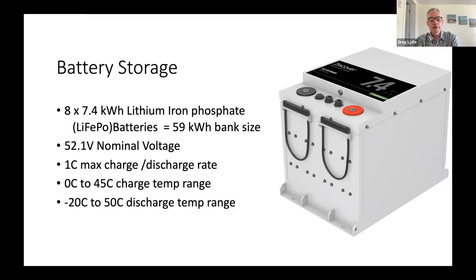The limiting factor here is the amount that the inverters can charge the batteries at, not the maximum charge current that the batteries can take. I think our inverters are rated at about 12.5 kilowatts for battery charging. So we could charge our system from essentially low batteries to 80% in about 4 hours of generator operation. I think the system's configured right now to charge the batteries up to about 80%. That can be tweaked up to 95% to get the full capacity of the batteries, but we typically run it at up to 80% to maximize the battery life over the course of the system.